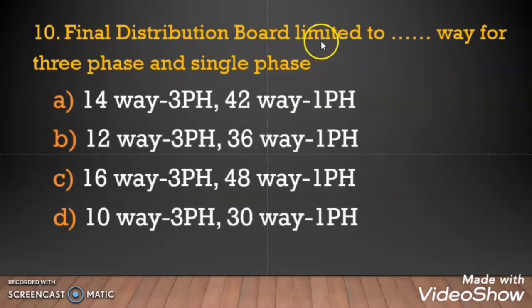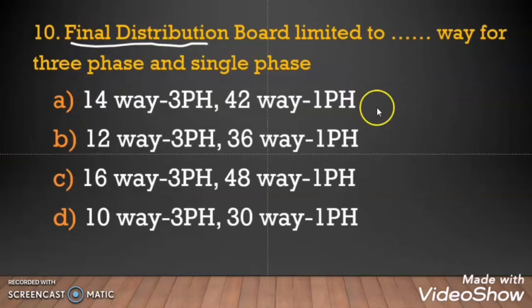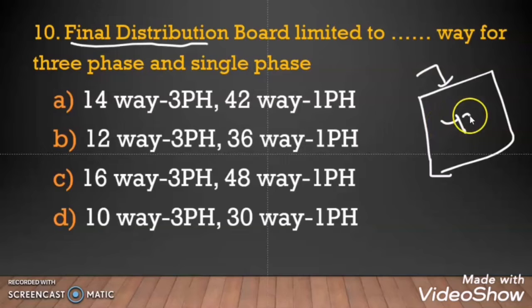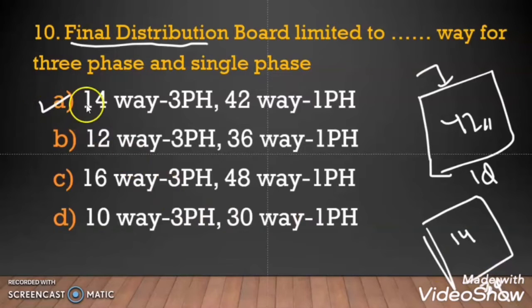Question 10: The final distribution board is limited to how many ways for 3-phase and single phase? As per ADDC regulation, 42 single phase circuits are allowed from one single phase final distribution board, and 14 three phase circuits are allowed from a 3-phase final distribution board. So the correct answer is 14 ways for 3-phase and 42 ways for single phase final distribution board.